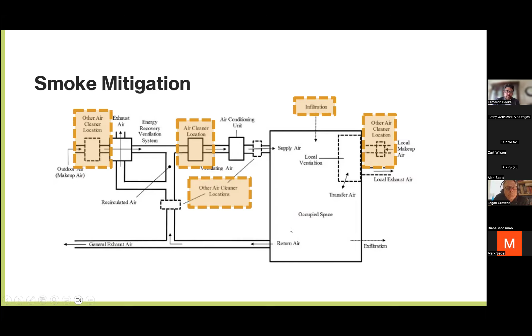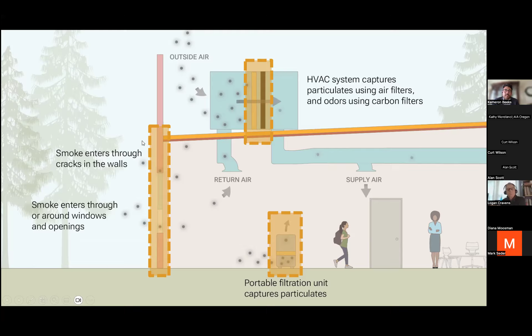Looking at a much cleaner, more architect-friendly diagram, that translates to these areas here: smoke can come in through the outside air system or an air handling unit system, which is supposed to pass across filters, and it can also come in through the facade. You'll hear me talk about portable filtration units throughout the presentation as potential strategies you could deploy, but the two largest areas where smoke can enter buildings are through the HVAC system and through the envelope.